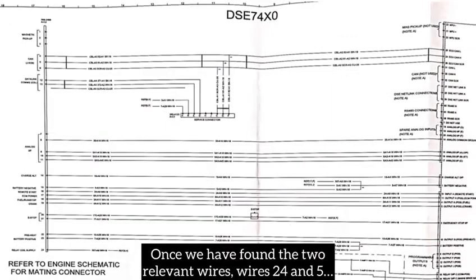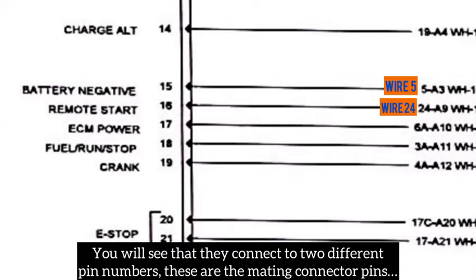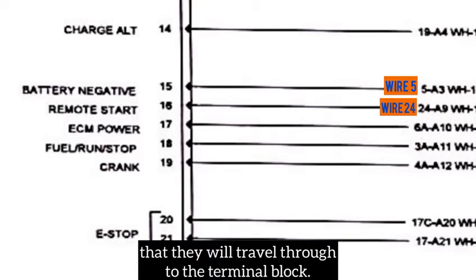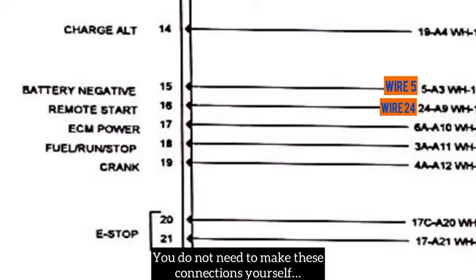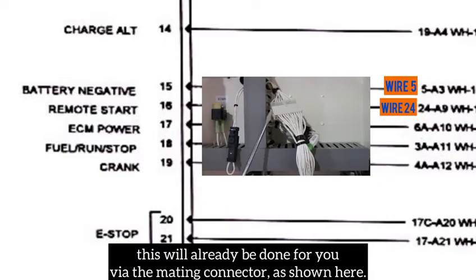Once we have found the two relevant wires — wires 24 and 5 — you can trace these wires on your schematic to the left column. You will see that they connect to two different pin numbers. These are the mating connector pins that they will travel through to the terminal block. You do not need to make these connections yourself; this will already be done for you via the mating connector, as shown here.